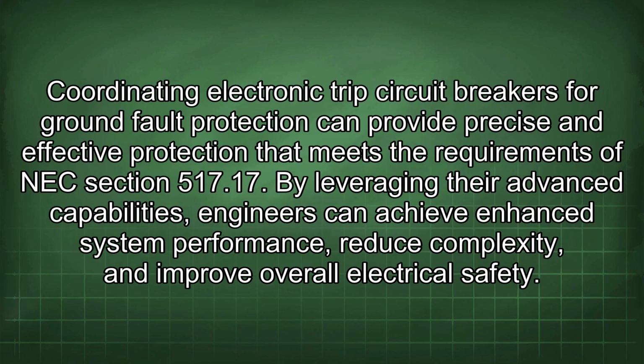Coordinating electronic trip circuit breakers for ground fault protection can provide precise and effective protection that meets the requirements of NEC Section 517.17. By leveraging their advanced capabilities, engineers can achieve enhanced system performance, reduce complexity, and improve overall electrical safety.